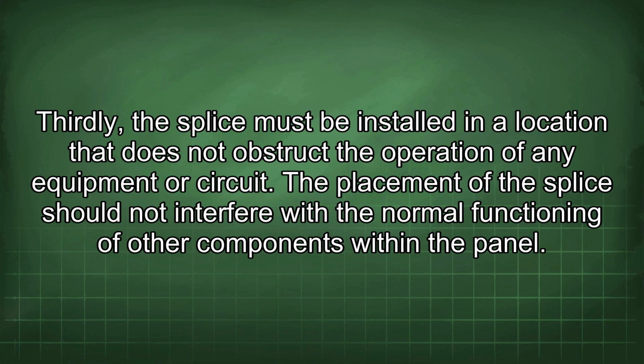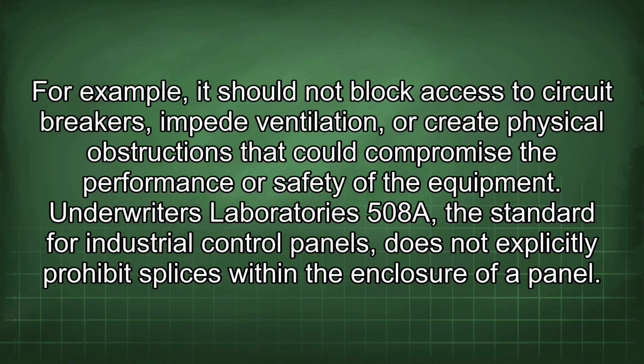Thirdly, the splice must be installed in a location that does not obstruct the operation of any equipment or circuit. The placement of the splice should not interfere with the normal functioning of other components within the panel. For example, it should not block access to circuit breakers, impede ventilation, or create physical obstructions that could compromise the performance or safety of the equipment.